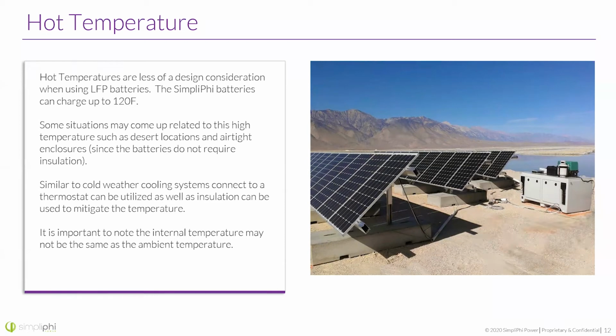And it is important, again, to note that the internal temperature may not be the same as the ambient temperature. That actually is funny because it actually plays the other way typically, meaning if it's really hot outside, probably the battery actually might be a little bit cooler on the inside. Definitely when it's operating, if it's charging, it might be a little bit warmer.